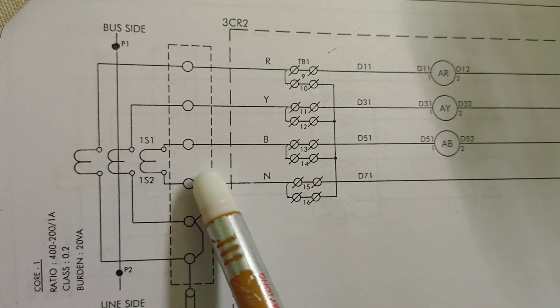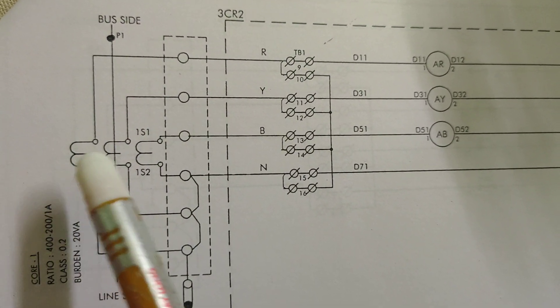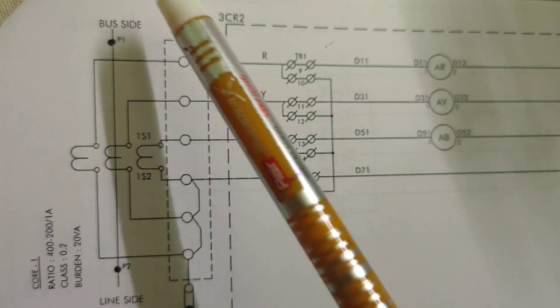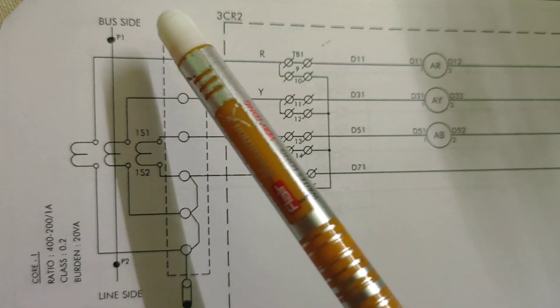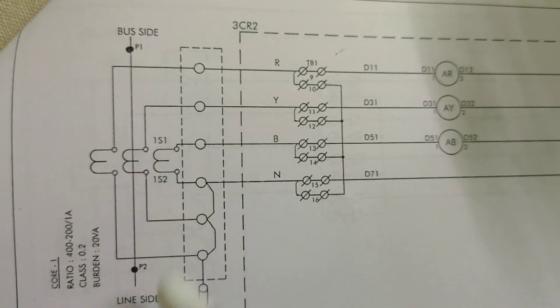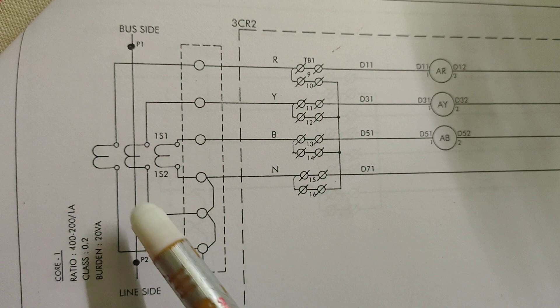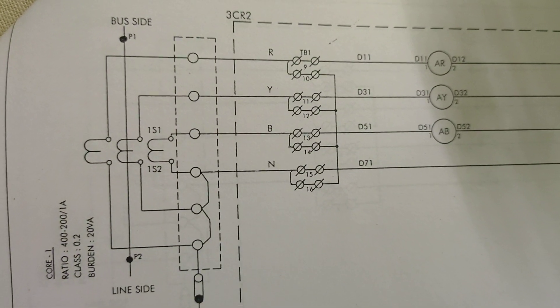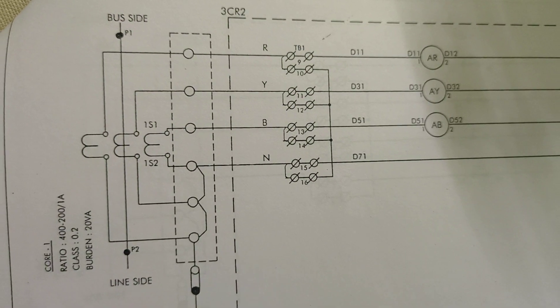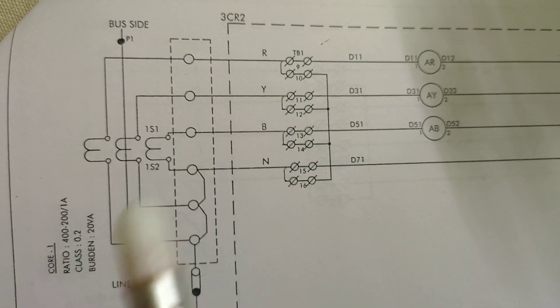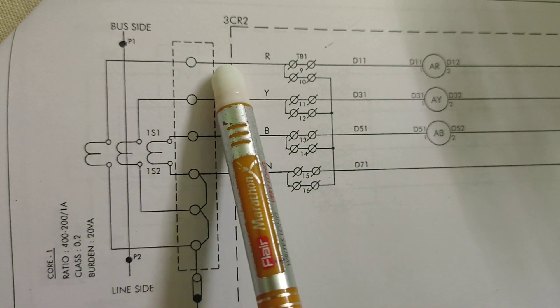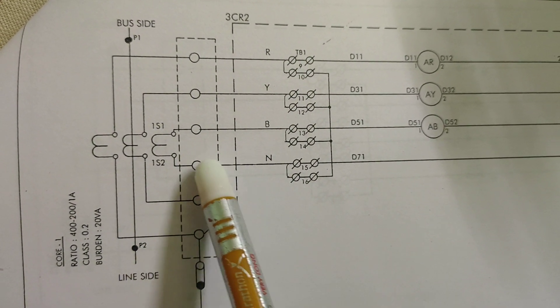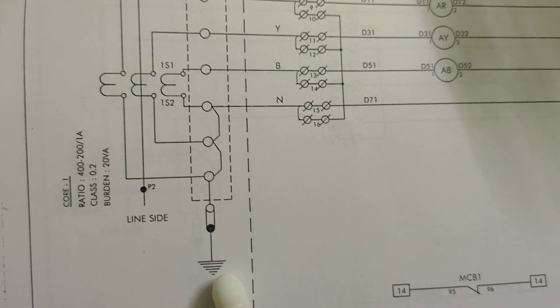Three-phase CTs are connected here: R phase, Y phase, and B phase. For simplicity, the Y phase CT P1 and P2 sides are shown — P1 is the bus side and P2 is the line side. The connections are in star configuration, and the S2 side of the CT is shorted and grounded.